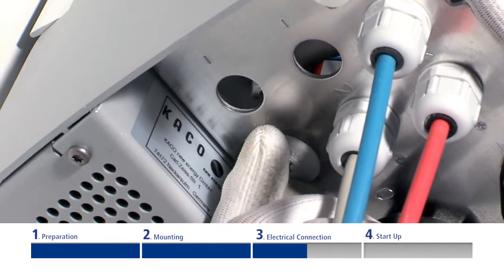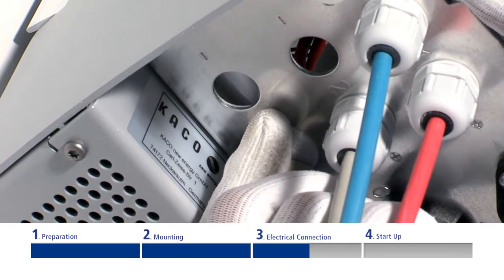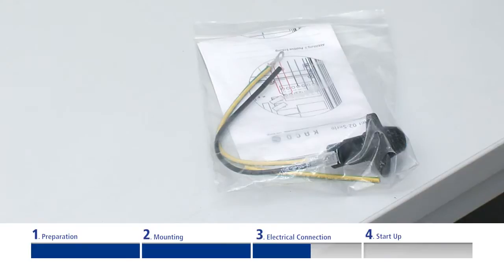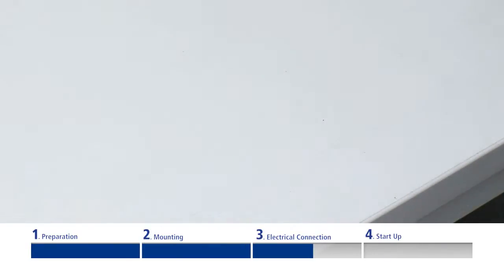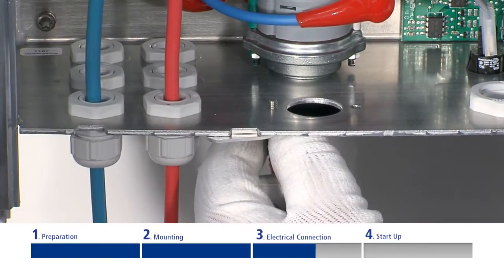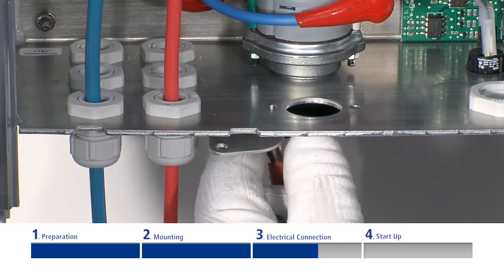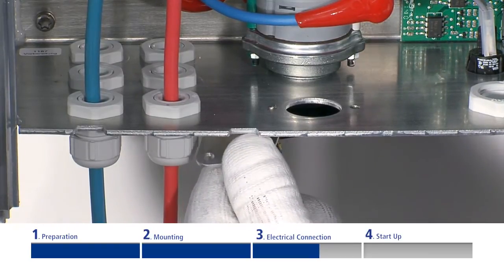Unused cable fittings must be closed off by using the protective caps which are included. Some module manufacturers, especially those of thin-film modules, stipulate earthing on the generator side. An optional earthing kit for use on galvanically isolated Powador inverters is available for this purpose.